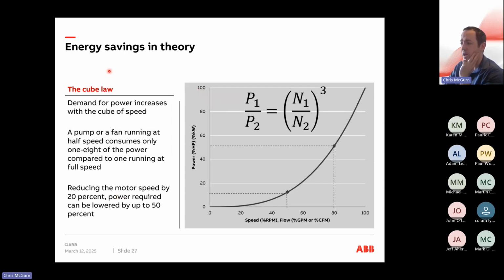So the cube law indicates that the demand for power increases with the cube of speed. So when a pump or fan is running at half speed, it actually only consumes an eighth of the power compared to running at full speed. So imagine a half is 1/2, so a half cubed is 1/8. So whenever you're running a pump at half speed, the level of savings becomes significant. It's because of the cube law. It leads to significant improvements in efficiency. So by reducing the motor speed by 20%, the power required can be lowered by up to 50%. So it is very significant and something to be aware of.